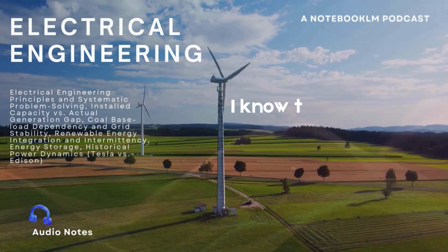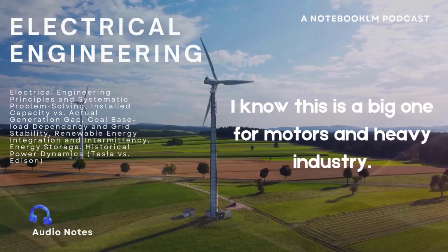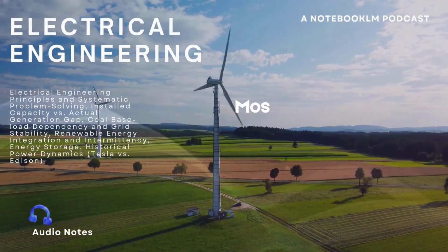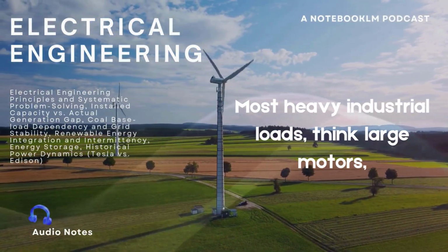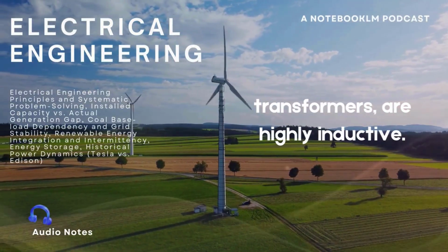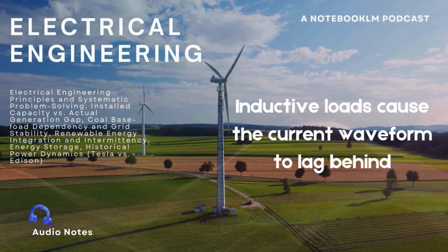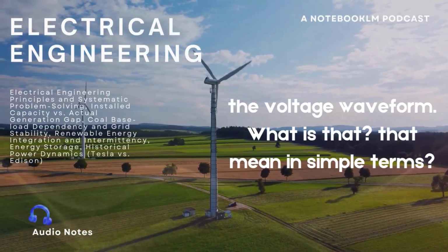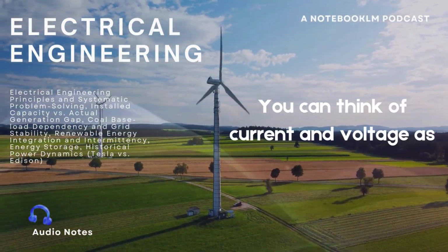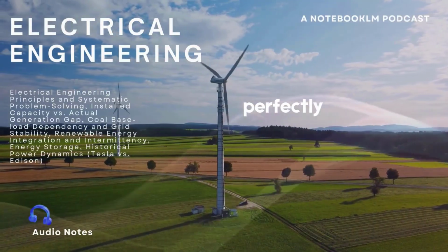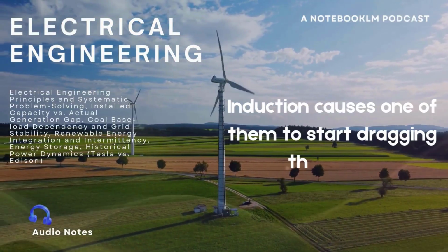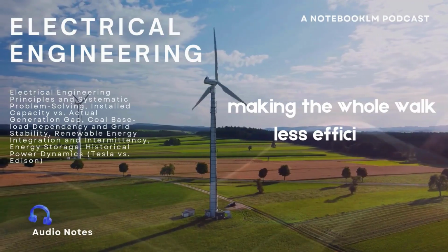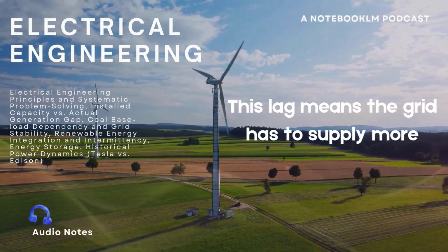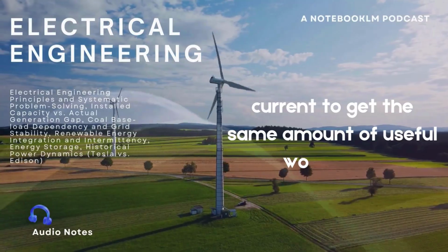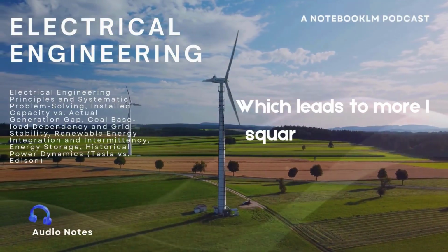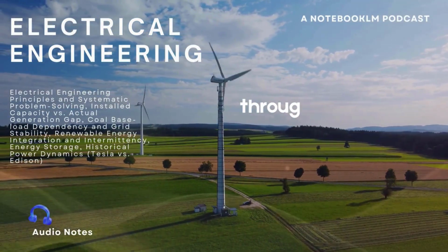And what's role number 2? I know this is a big one for motors and heavy industry. It is. That's power factor correction. Most heavy industrial loads, think large motors, transformers, are highly inductive. Inductive loads cause the current waveform to lag behind the voltage waveform. What does that mean in simple terms? You can think of current and voltage as two people walking perfectly in rhythm. Induction causes one of them to start dragging their feet, making the whole walk less efficient. This lag means the grid has to supply more current to get the same amount of useful work done. Which leads to more I²R losses all through the system.